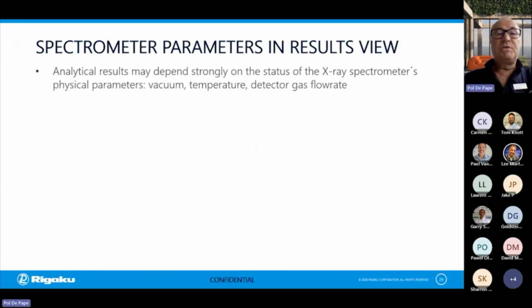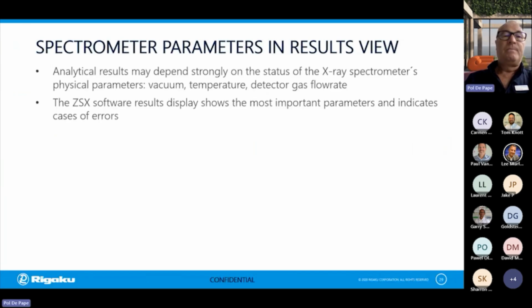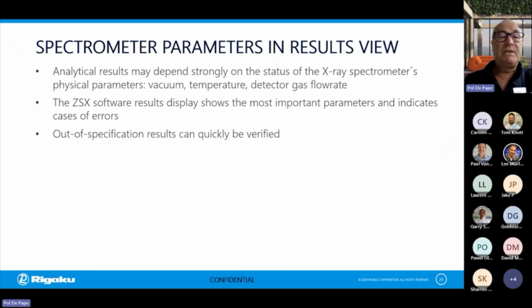We can also see some spectrometer parameters in the results view. So analytical results may depend on some parameters of the spectrometer, like the vacuum, the temperature, the detector gas flow rate. The software will now show those parameters in the results window.